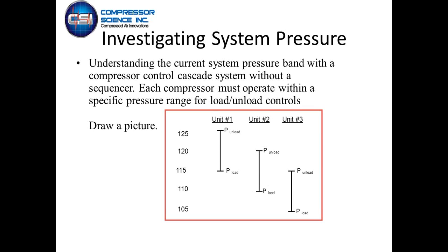Again, this is looking at a pressure band in the compressor cascade system where there is no sequencer, there is no integrated controls between the machines. On an unload-load basis, you really have to cascade an operation, for example, here between 3 compressors to a point where you've got those compressors that are working within a pressure band.